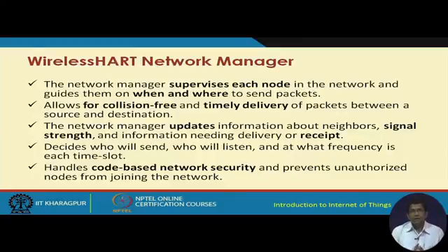Wireless HART uses something known as the network manager agent. The network manager agent supervises each node in the network and guides them when and where to send the packet, when to send the packet and what the intended destination is. So, this is the job of the network manager entity in wireless HART. This network manager allows for collision free and timely delivery of packets between a source and the destination. The network manager updates the information about the neighbors, the signal strength and the information needing delivery or receipt.